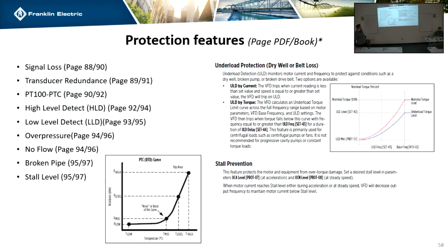What was I after? 92. Oh, 94, 95. Just want to make sure. Okay, so the high-low detection is what we used to call stall. So the high level, if you get above that, before tripping, the drive will start stalling the load out and dropping it down to keep the amps down at your set point before it trips. So it'll try to keep it running as long as it can. Low level detect.